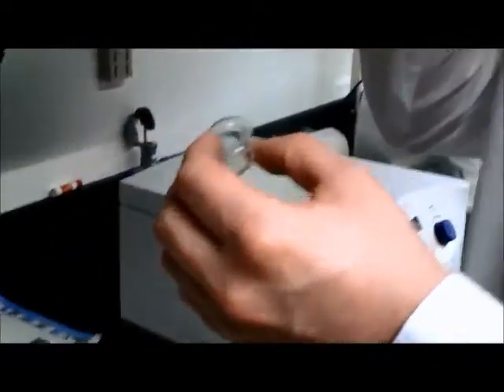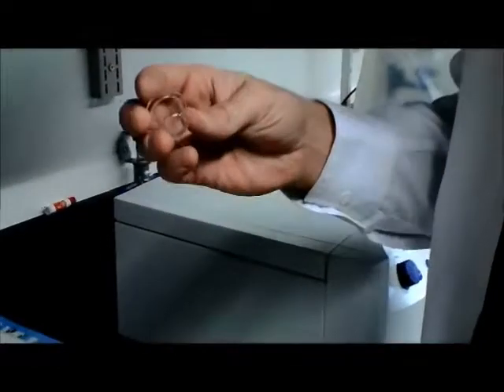going to contain our sample. Does that limit our sample size then? This does limit our sample size. Sample size is limited no matter what. You really need to try to keep, hopefully you have an idea of what the energy is worth. I can't put my foot in there? No, you can't put your foot inside of this. They do make larger ones, but you still have to keep it under 40,000 joules per gram. There's a limit to the total energy because there's a safety issue there.